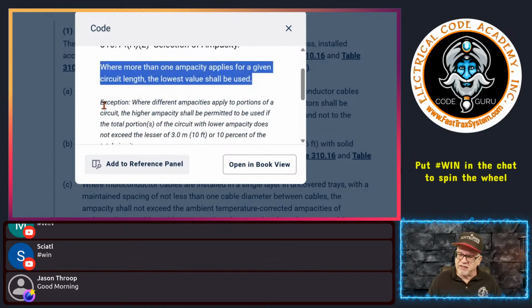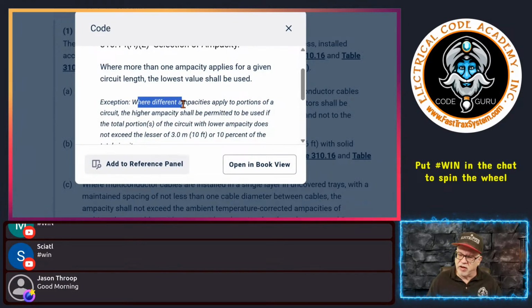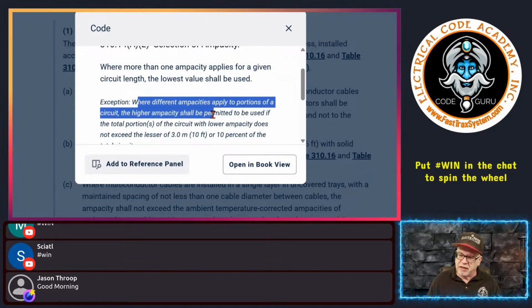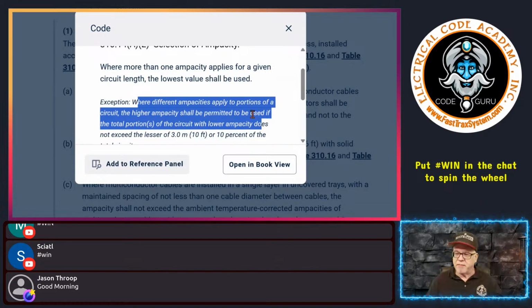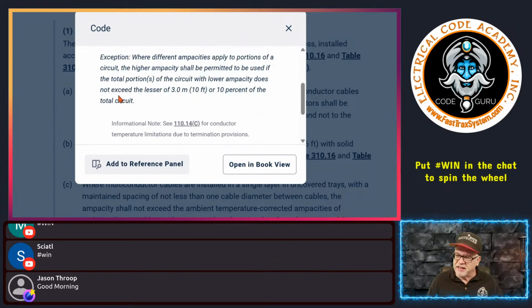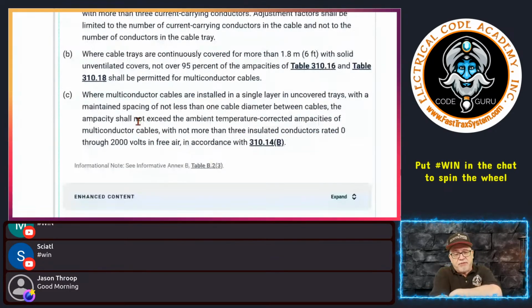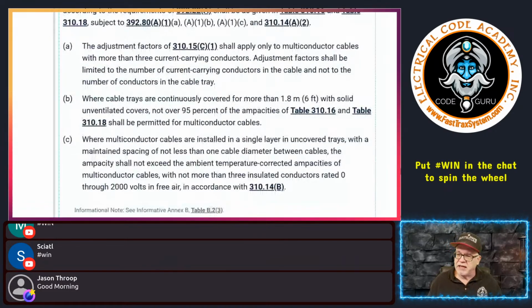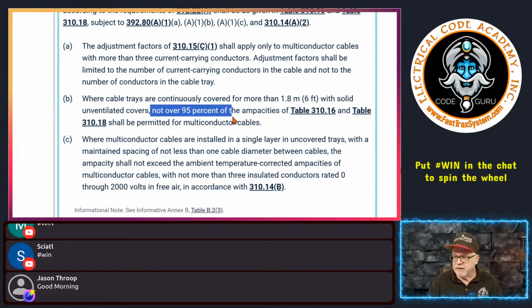Okay, and this allowance says exception where the different ampacity applies to portions of a circuit. It says the higher ampacity shall be permitted to be used if the total portion of the circuit with lower ampacity, that is that 6 foot, by the way, does not exceed the lesser of 10 feet or 10% of the total circuit, okay? So important as a design professional, maybe not for us, maybe you don't run into this very often, but if it's only 6 feet of it and you're restricted down to 95% of the ampacity, then 310.14(A)(2) and the exception may help you ignore that small portion.